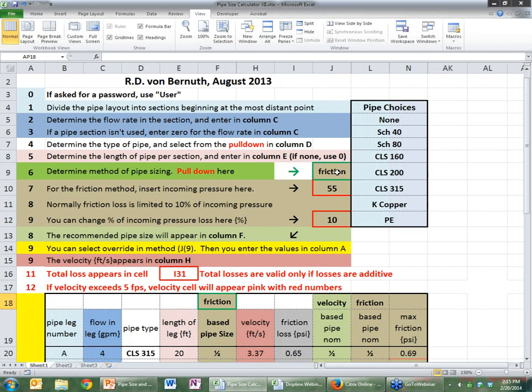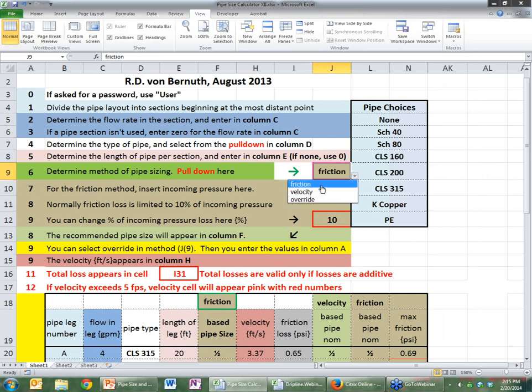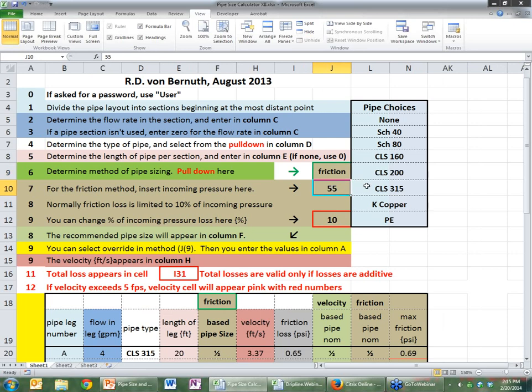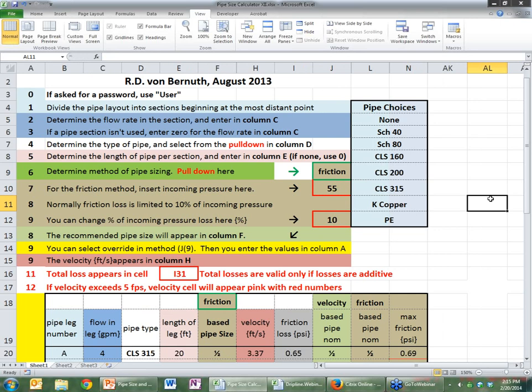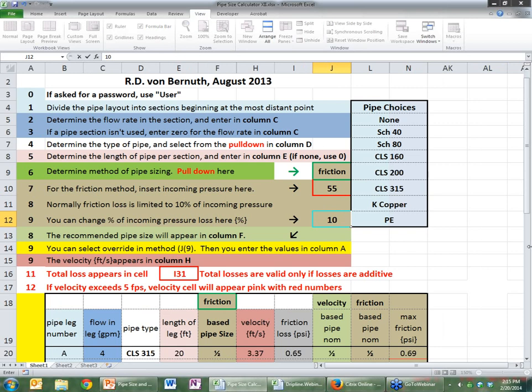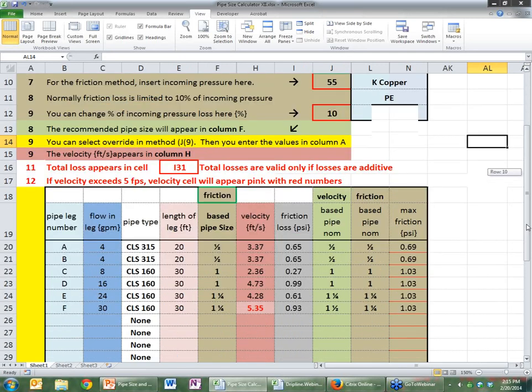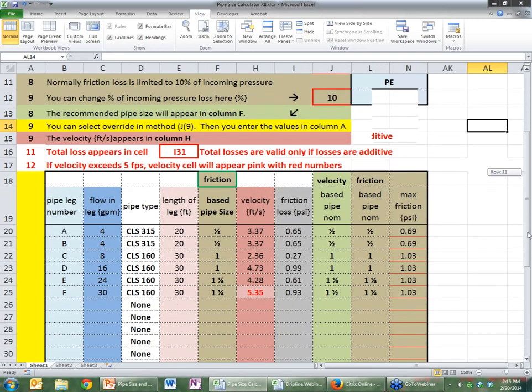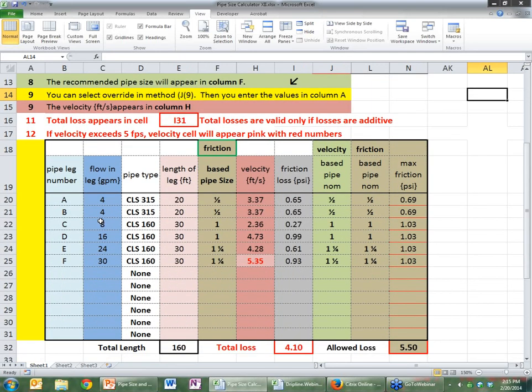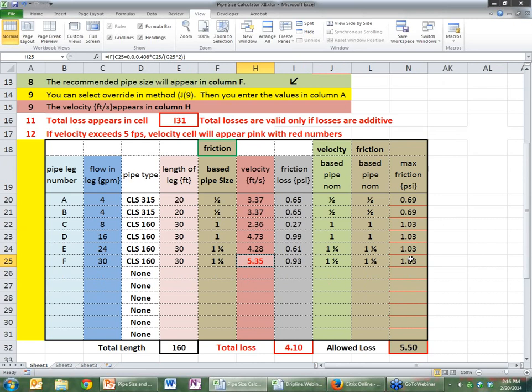Now, so the first thing we do is we determine which method we're using, and we're using friction. Just to show you here, you can choose friction, velocity, or override. So we've chosen friction. In the friction method, you insert the incoming pressure, and this you type in. So in this case, it's 55. We've typed it in. We normally use 10% of the loss, and that's what I've defaulted to as 10% right here.